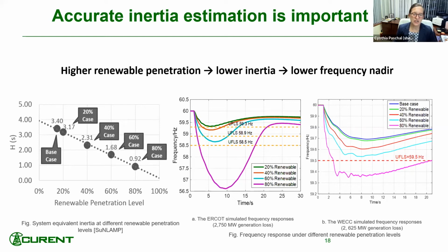What are some of the measures used for damping the oscillations? In the generator, you have a governor control. And say you have an energy storage—you can control it very fast to inject power or absorb power. Basically, damping control can quickly push power out and absorb it in the counter phase of the oscillation. That's actually an actionable and helpful process. Many FACTS devices, HVDC lines, and synchronous condensers are all capable of either injecting real power, absorbing real power, or reactive power to help the grid calm down, what we call damping.